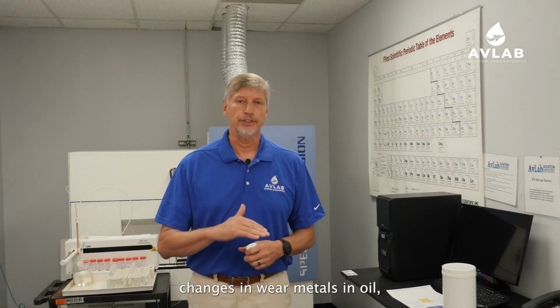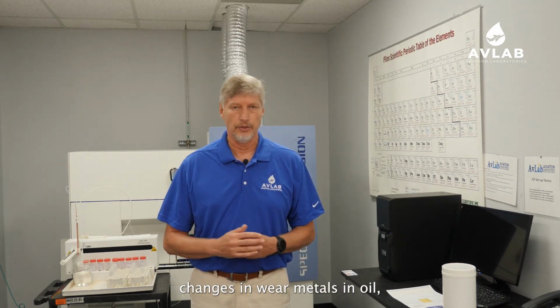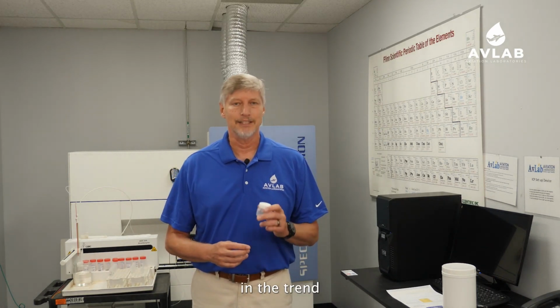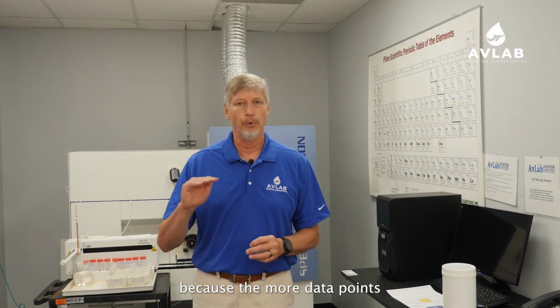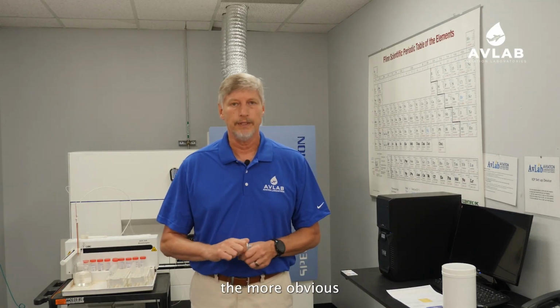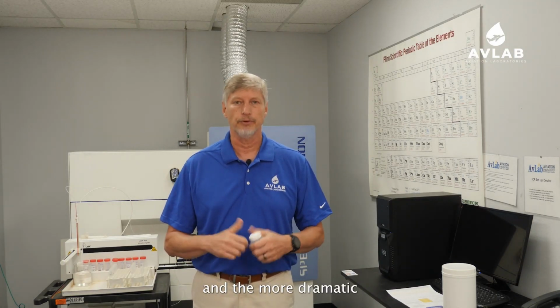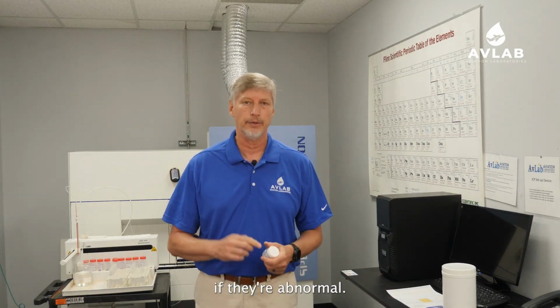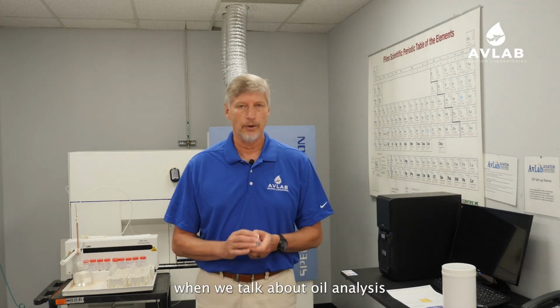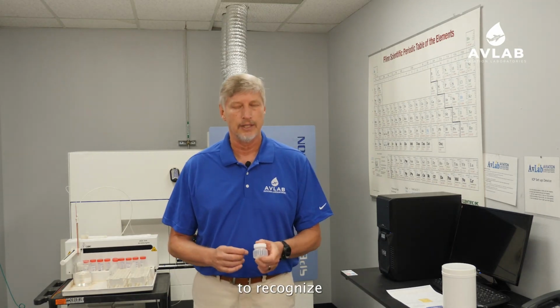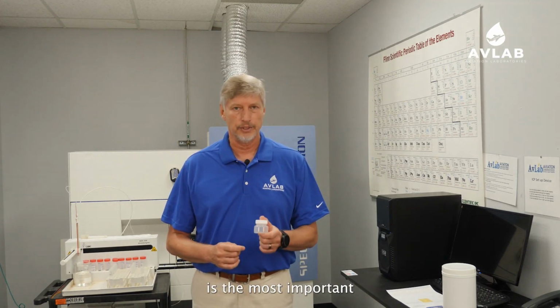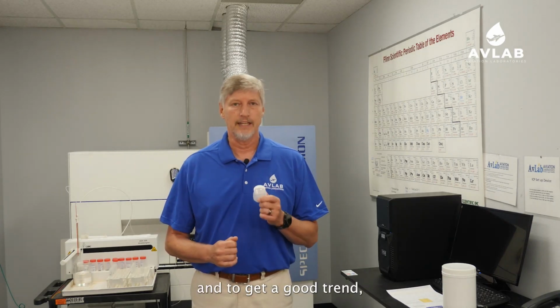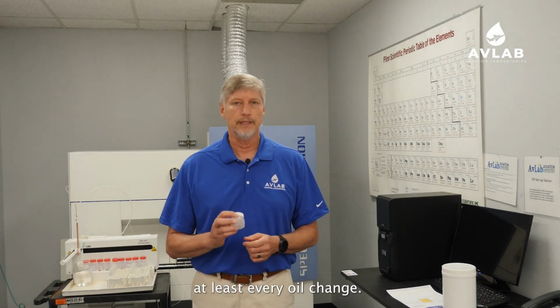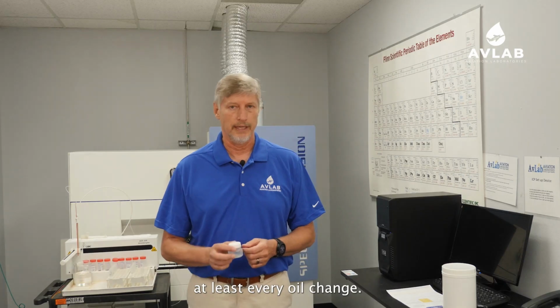Obviously, if we're looking for changes in wear metals in oil, we're also interested in the trend, because the more data points we get, the more obvious the changes become, and the more dramatic the changes become if they're abnormal. So it's important for us, when we talk about oil analysis, to recognize that the trend is the most important part of that, and to get a good trend, you should do it at least every oil change.